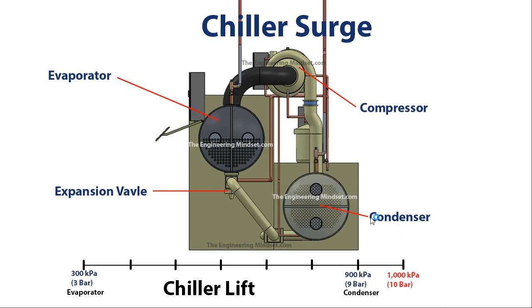When chiller surge occurs, the pressure in the condenser has become too great and the refrigerant starts to push back, flowing back through the discharge line and into the compressor in the opposite direction. The compressor will still continue to rotate, still trying to push refrigerant into the discharge line and into the condenser, but the pressure is already too great, so the refrigerant flows back through into the impeller blade and out through the suction line into the evaporator. This is not a good scenario — it can cause some really serious damage to the chiller.